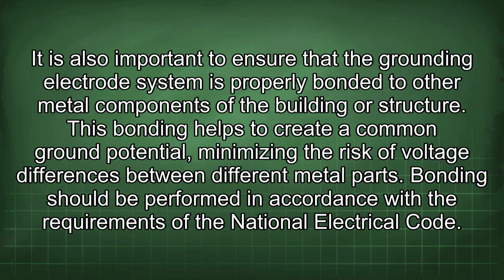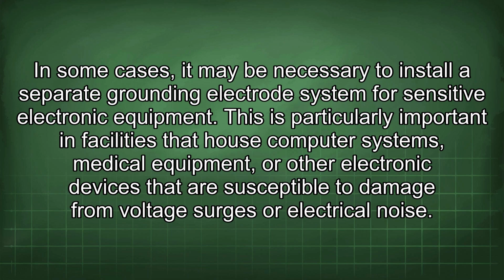It is also important to ensure that the grounding electrode system is properly bonded to other metal components of the building or structure. This bonding helps to create a common ground potential, minimizing the risk of voltage differences between different metal parts. Bonding should be performed in accordance with the requirements of the National Electrical Code. In some cases, it may be necessary to install a separate grounding electrode system for sensitive electronic equipment. This is particularly important in facilities that have computer systems, medical equipment, or other electronic devices that are susceptible to damage from voltage surges or electrical noise.